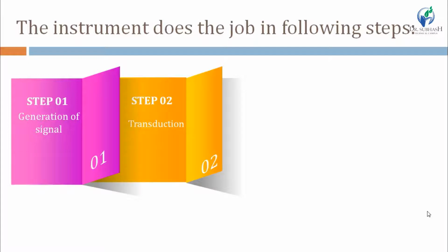Transduction is done by transducers, and very popular transducers are photocells, thermocouples, and PMT, photomultiplier tubes, used in analytical instruments.